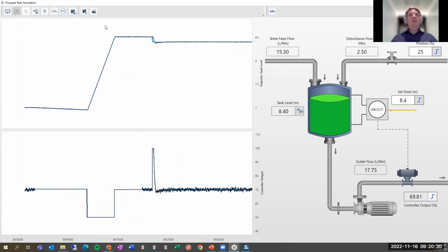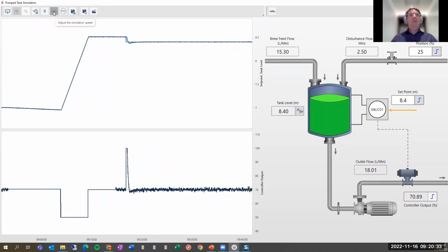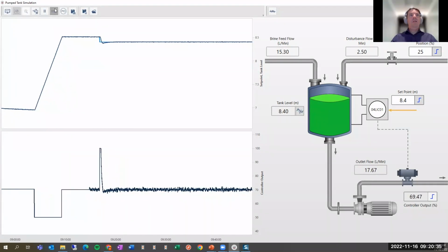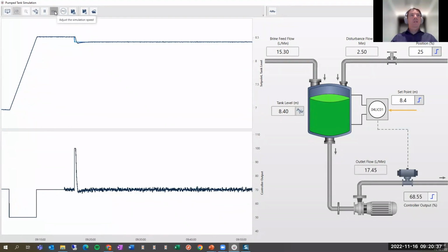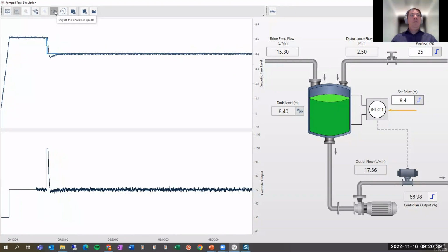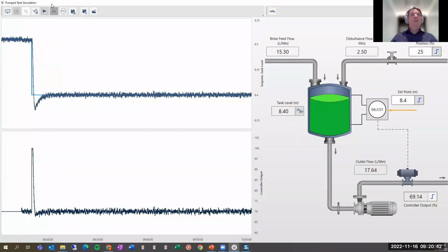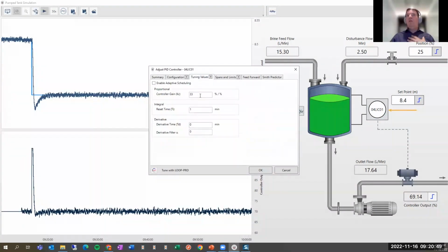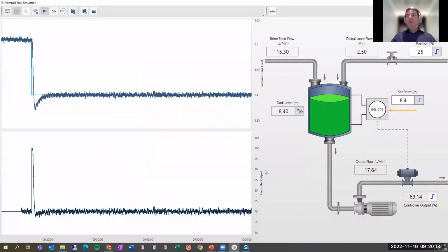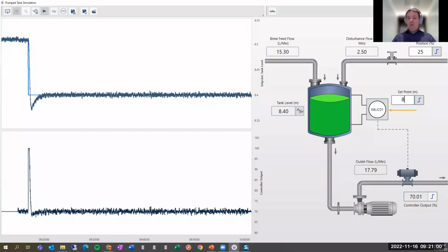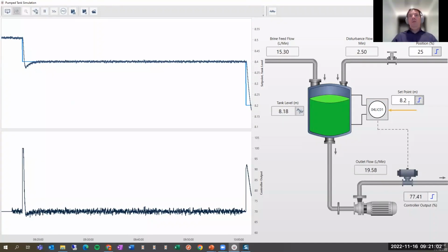I will just let it go to get rid of the previous one, just so we see better. You'll see it looks better soon. All right. So you see the overshoot. So the reflex, and we'll test it, would be like, oh, well, I will try to cut down my gain, right? So I'll cut down my gain a lot and we'll see the impact. So I will cut my gain. I will go 8.2 and see the type of response.